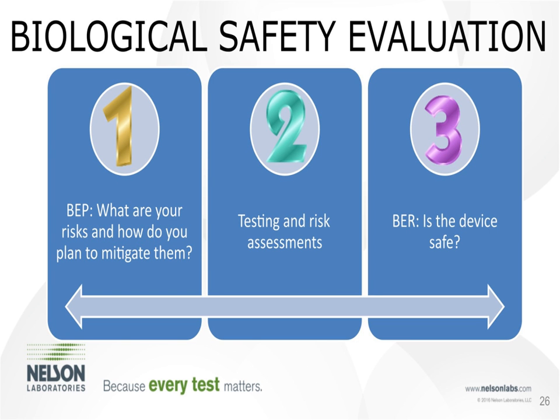In summary: Step one is a biological evaluation plan — identify your risks and how you're mitigating them, and remember it's not a checklist approach. Step two is testing and risk assessments — perform the testing and do risk assessments where necessary. Dr. Campbell pointed out the price and time benefits of extractable and leachable testing with risk assessment versus all animal testing. Step three is the biological evaluation report — identify if your device is safe. Do not leave room for assumptions for reviewers, as they simply won't make them. Make your justifications and support biological safety through to the end.